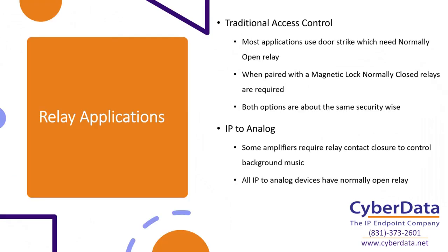The two main relay applications we'll talk about are traditional access control and IP-to-analog solutions. In traditional access control, you're going to use a door strike, which uses a normally open style relay. The more common option is a door strike where when the system is not engaged — not electrified — it's in the locked position. You engage it, electrify the system, complete the circuit, and the door is unlocked. This is the most traditional option because it doesn't require any energy to stay in the physical locked state.